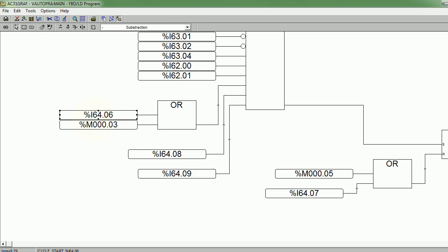You really need to go to your system engineers, maybe to the system house, and get the documentation for that PLC. So that you can know that, if it is input I64.06, what is the real Modbus address for it? If this is memory bit 000.03, how does that address in the PLC program really translate to a Modbus address? That is something that varies PLC to PLC, and that's one thing you need to know.